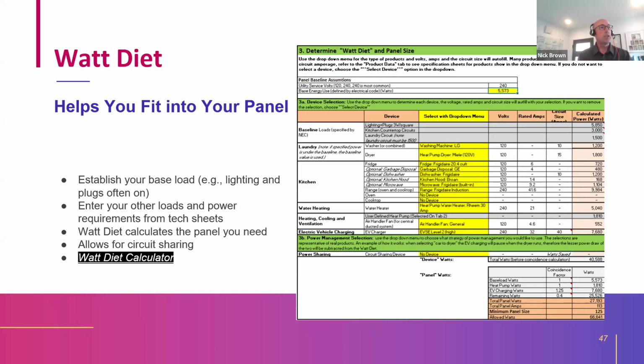Then you just fill out this spreadsheet. The gray parts come automatically from the base load calculations based on your square footage. You tell it what you're planning to install or what you currently have, the volts and amps that those require. It automatically applies the coincident factor of 0.4 to those loads that qualify for it, adds it all up.